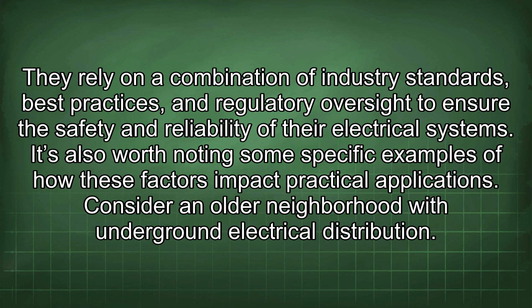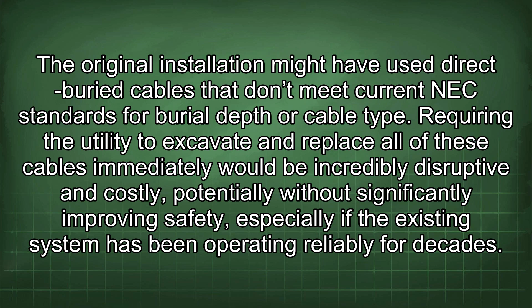It's also worth noting some specific examples of how these factors impact practical applications. Consider an older neighborhood with underground electrical distribution. The original installation might have used direct buried cables that don't meet current NEC standards for burial depth or cable type. Requiring the utility to excavate and replace all of these cables immediately would be incredibly disruptive and costly, potentially without significantly improving safety, especially if the existing system has been operating reliably for decades.